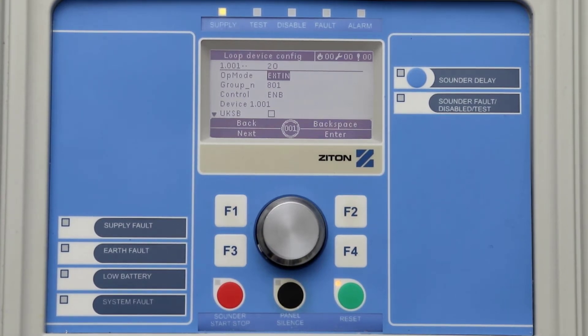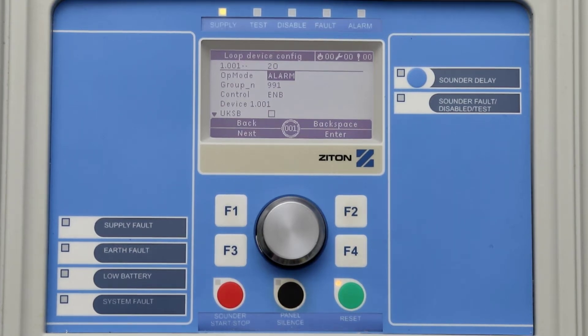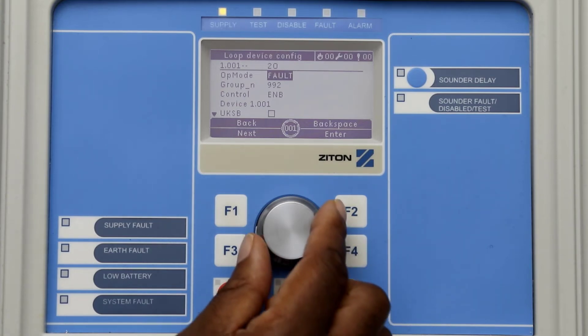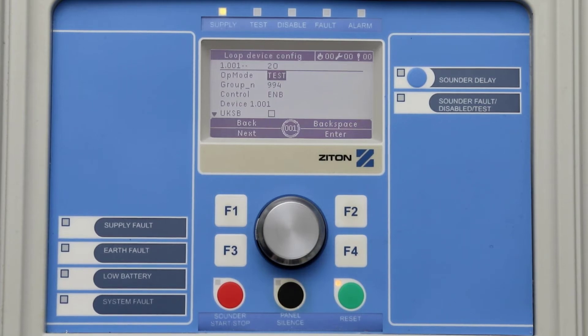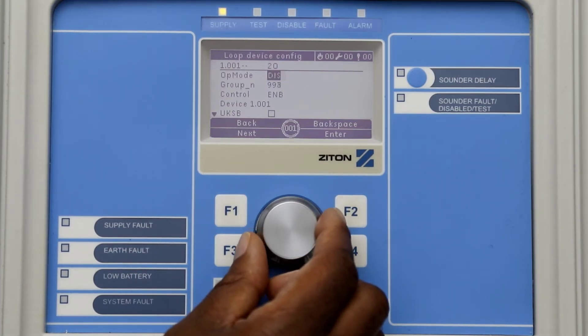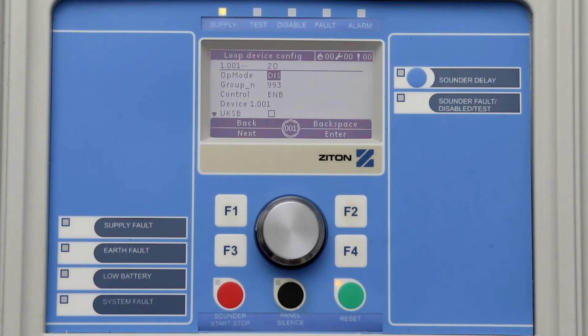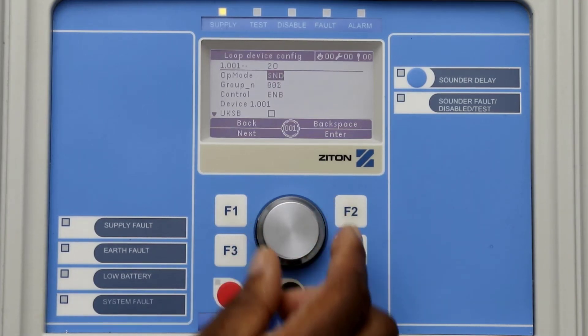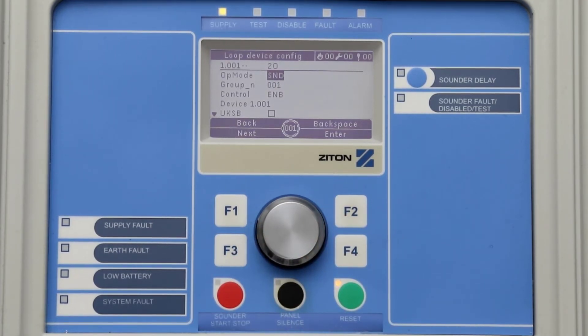The next option is Alarm — if the relay is configured using this option, the relay will be active if the alarm LED is on. The next option is Test — if configured using this option, the relay will be active if the test LED is on. The next option is DIS, which stands for Disable — the relay will be active if the disable LED is on. The next option is SND — when using this option, pressing the sounder start/stop button will deactivate the relay.